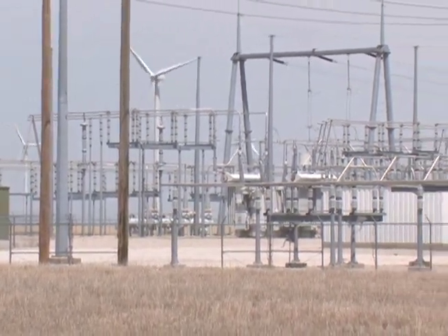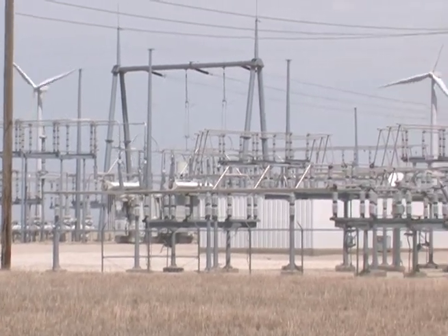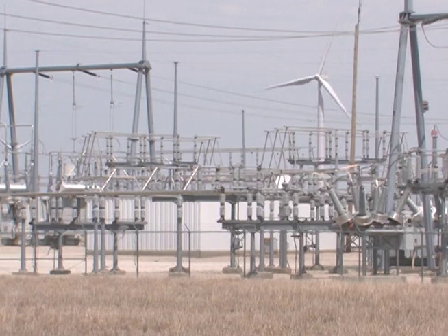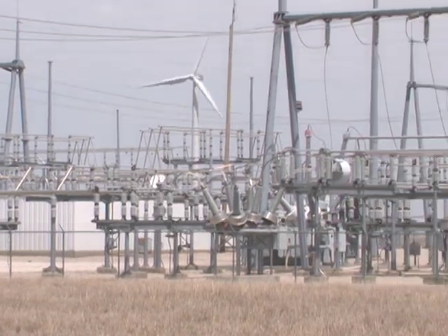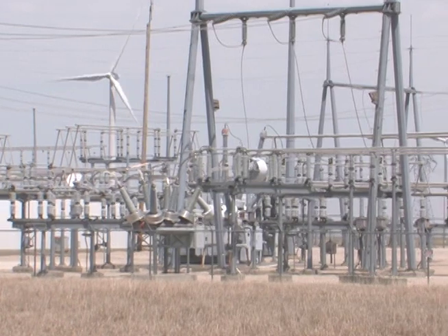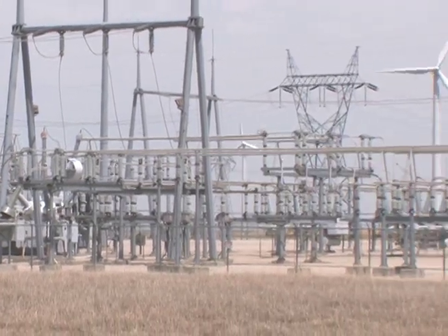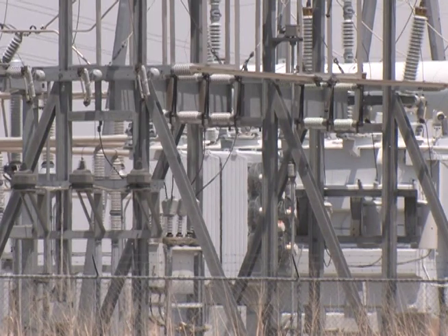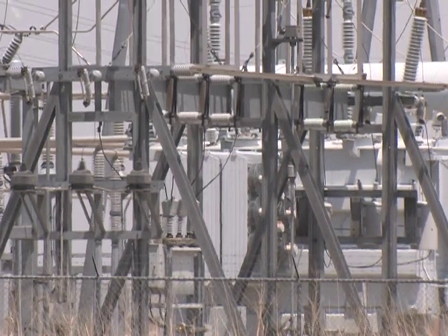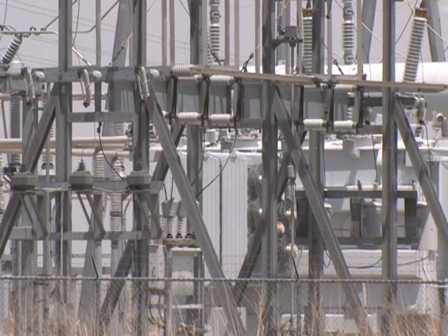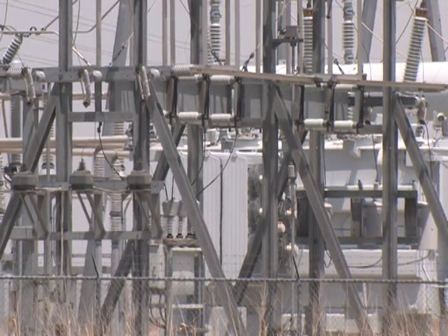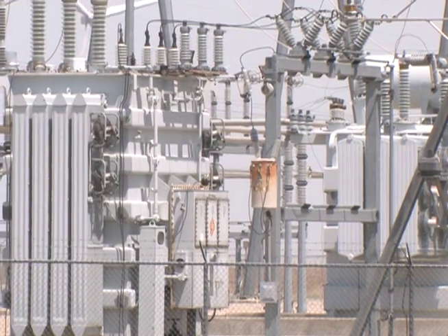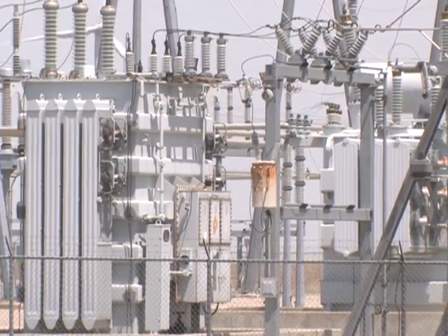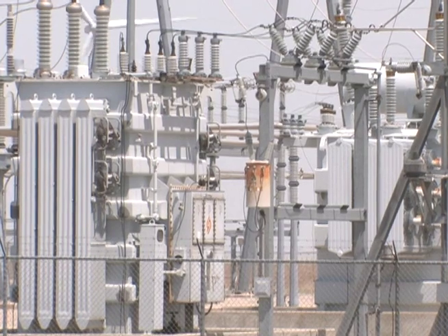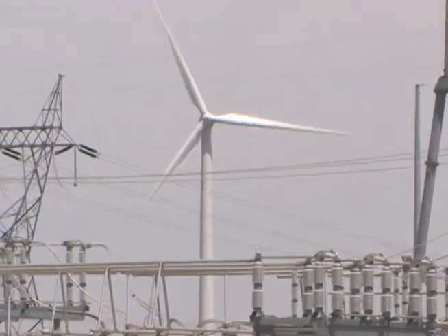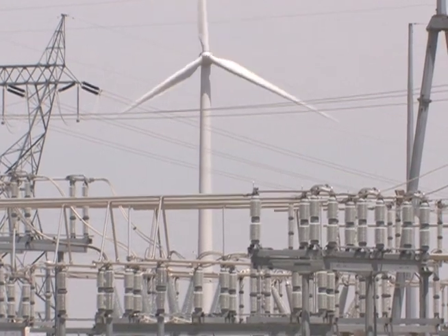What you're viewing here is a typical high voltage transmission substation. Within it you have protective devices to protect the equipment and the transmission lines, and transformers which step up or step down the transmission voltage. We generate wind at 34.5 kV, and to step it up to 345,000 volts, you need a transformer — you'll see those devices in this substation. It's a typical substation with line terminals for 4 or 5 incoming lines, a couple of transformers, and all the protective equipment.